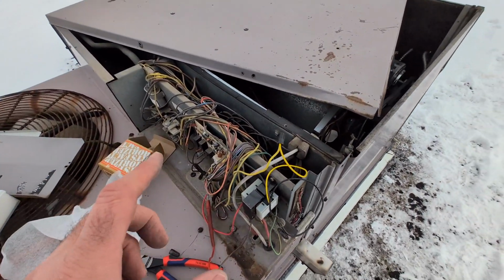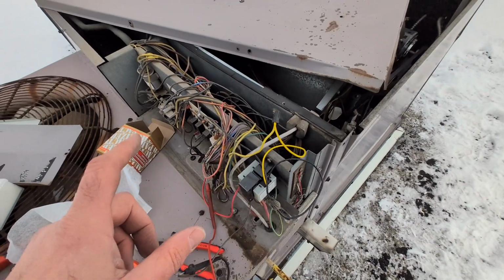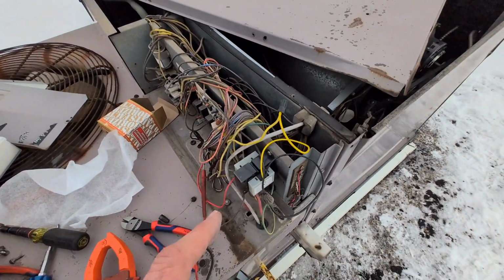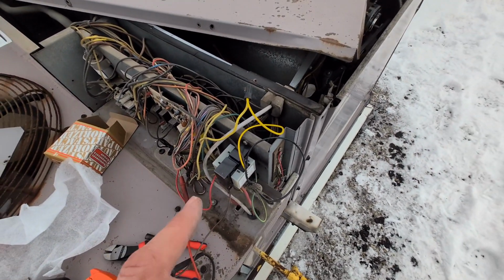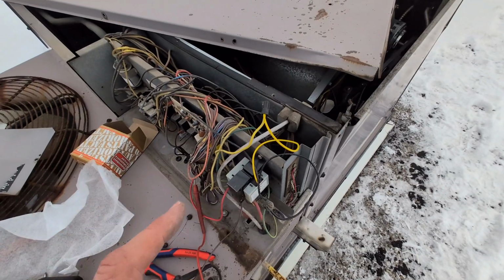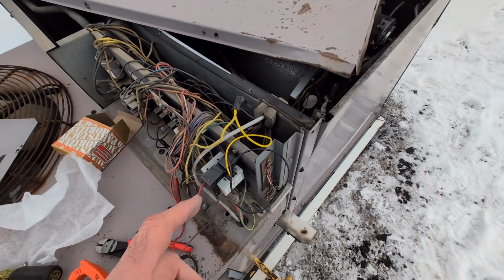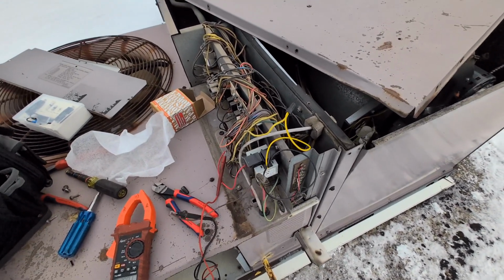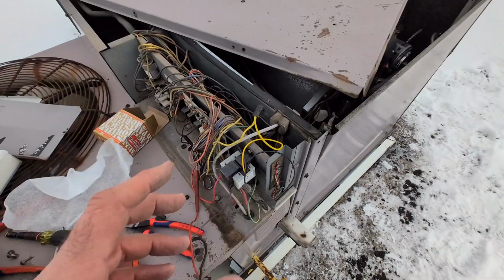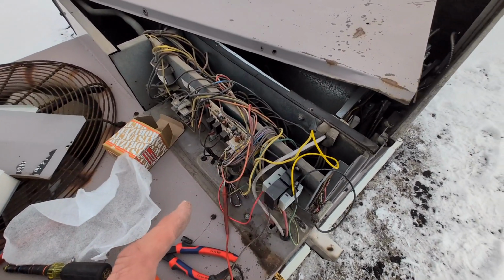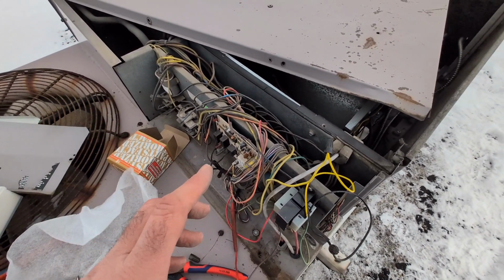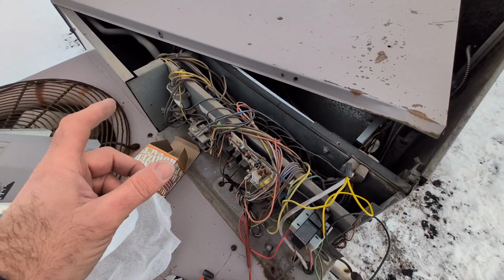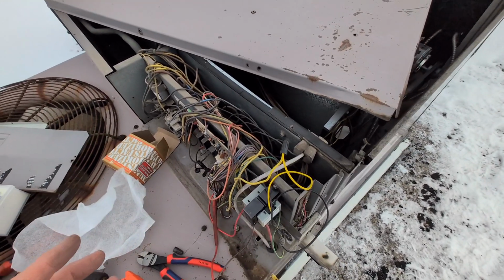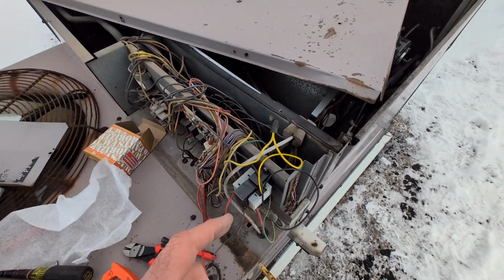Whenever you put in a transformer, you always want to fuse it, all right, or get a transformer that has a built-in breaker that's resettable. Unfortunately, they didn't have one that had a resettable breaker, so I picked up some fuses and an inline fuse holder because there could be something else wrong in the system. So you want to make sure that you have it fused, because if you have a bad contactor coil, a bad board or something like that, it could take the transformer out.